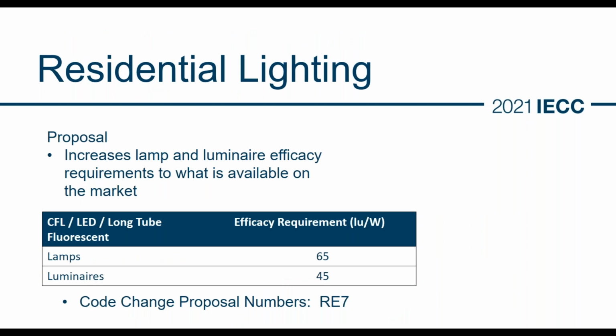So we have had lighting efficacy requirements in the code since I think 2009 that basically say that if you put in a connected light, it has to meet a certain lighting efficacy requirement in lumens per watt. And so it really got us away from incandescent and into compact fluorescent lighting. The code values have gone up from 50%, then to 75%, then I think the 2018 IECC is now up to 90% high efficacy lighting in buildings.